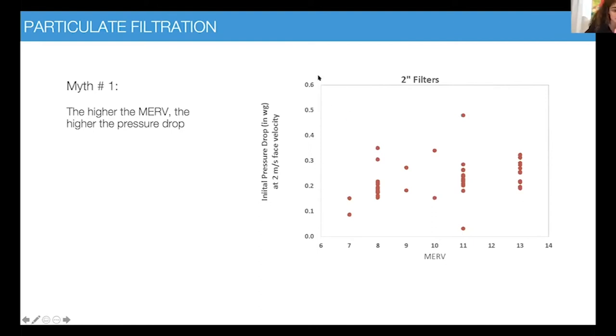On the y-axis is the pressure drop. On the x-axis is basically the different MERV category. So the higher the MERV category, the higher the efficiency. For the sake of the comparison, I made all of them at the same face velocity and basically the same depth of the filter. So two takeaways from this slide. The first one is that you can have the same MERV 13, and you can see here the range of the different filters, the range of pressure drop. So if you have a MERV 13, you need to dig deeper in the test data to know what the pressure drop is, because it can vary. So MERV is not equal MERV. This is myth number one.